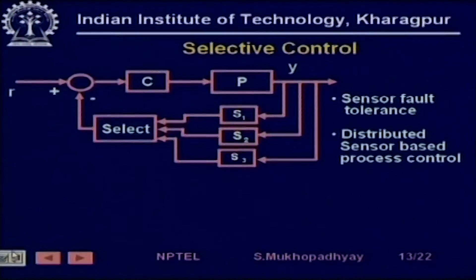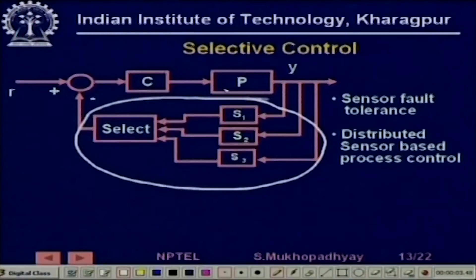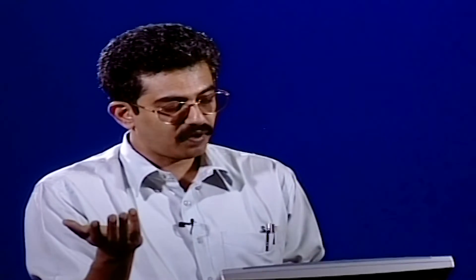In selective control, the loop is standard — the only change comes in how sensor signals are handled. What we have shown is that the same process variable, for example room temperature, is being sensed by three different sensors at three different locations. So these signals are not identical, but they will be similar. There is some selection or signal processing scheme applied here.